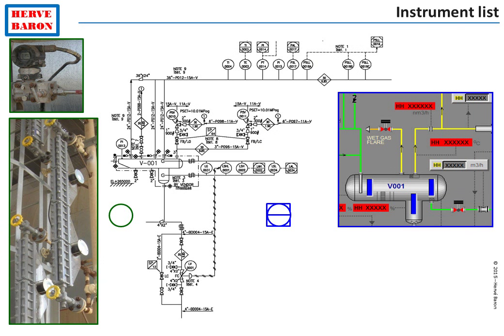The starting point of the discipline is the P&IDs. On the P&IDs, process has shown all instruments required for monitoring, control and shutdown. For monitoring, process also specifies if the measurement shall be locally available or available remotely from the control room. There are two types of instruments: field instruments, depicted on the P&ID by means of a circle such as a pressure indicator, and virtual — also called soft — instruments, which are displays on control system screens or signals inside systems. These instruments are depicted on the P&IDs with a square frame.